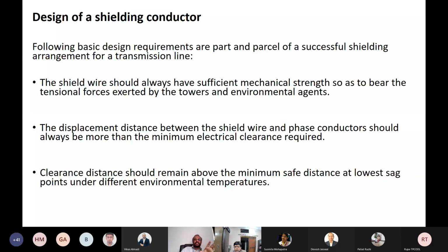It may be a transmission line or distribution line, it's the same criteria. The shield wire should always have sufficient mechanical strength so as to bear the tensional forces exerted by the towers and environmental agents. The displacement distance between the shield wire and phase conductors should always be more than the minimum electrical clearance required. Then the clearance distance should remain above the minimum safe distance at lowest sag points under different environmental temperatures.